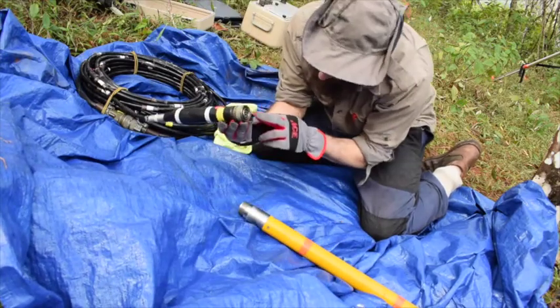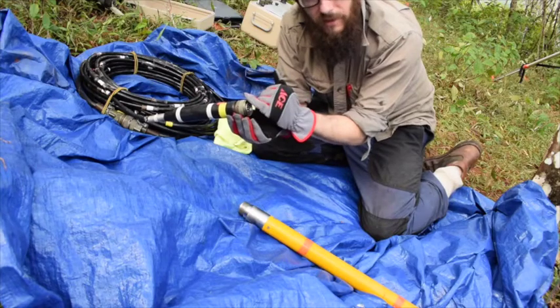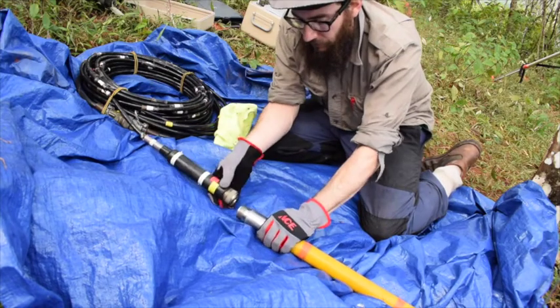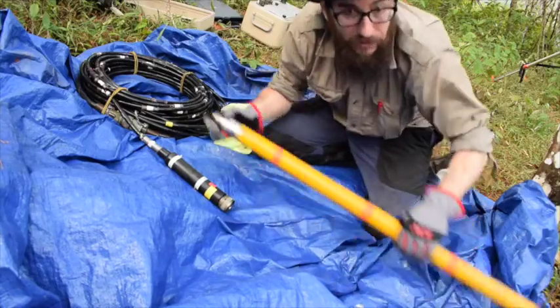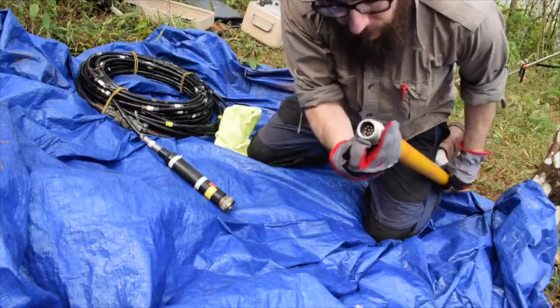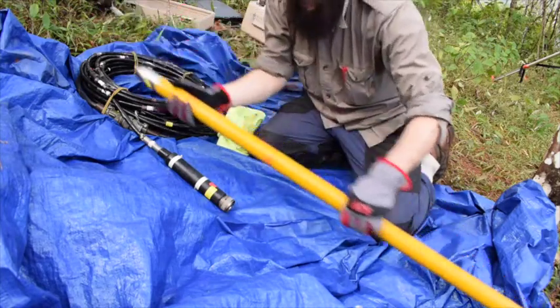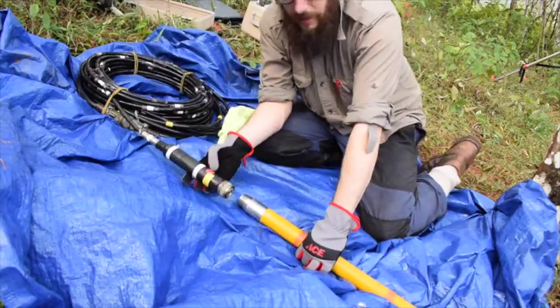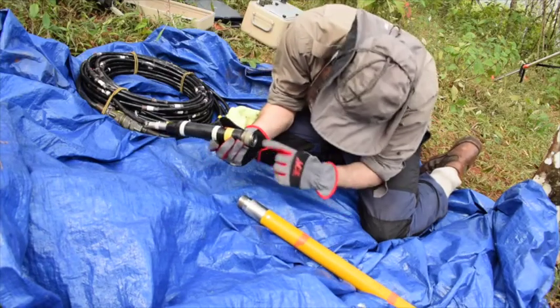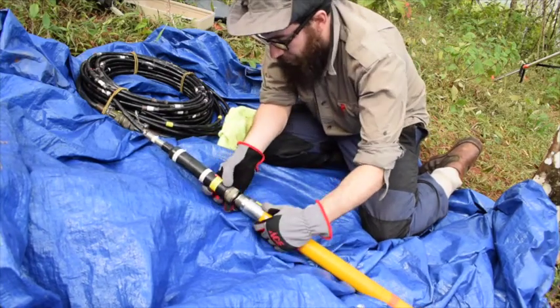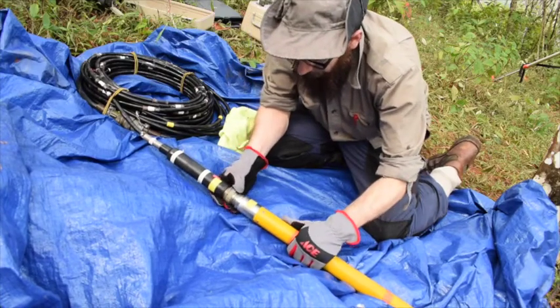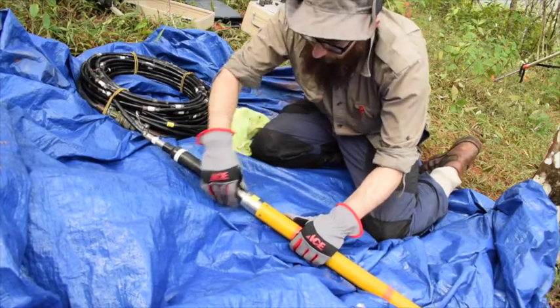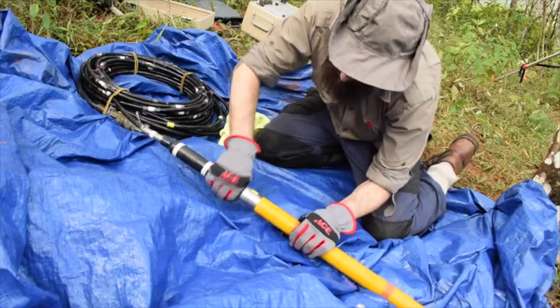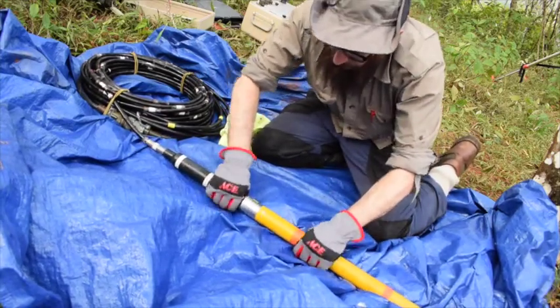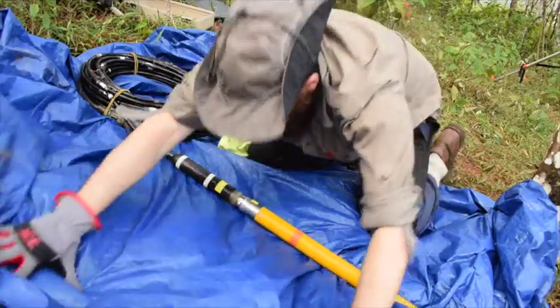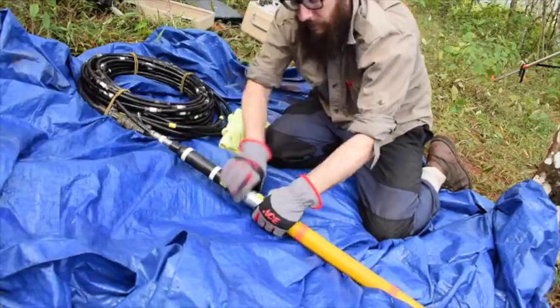And so the other thing is that inside the cable head there are 2 little bumps that key the direction of the cable head so that the probe connects correctly. And there are 2 slots on the probe, you can see right there and there, that fit into those bumps. So never rotate the cable, always just rotate the probe. It's easiest to just look in ahead of time and see which direction those bumps and slots are. And then once you line them up, you can screw it on. And it will very quickly pull the probe towards the cable, and so you know you've done it right if the probe and cable are well connected.